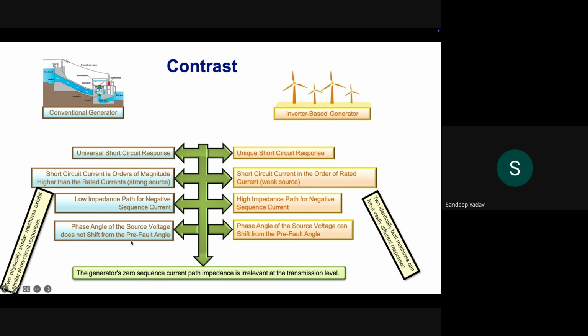And later in the last, we have a predictability in terms of the phase angle between the voltage and current at the time of fault. Because the synchronous machines act as a voltage source behind reactance, the current that it feeds usually is lagging in nature when it is compared with the voltage. However, in case of an inverter-based resource, the phase relationship between voltage and current could be anything depending upon the algorithm.